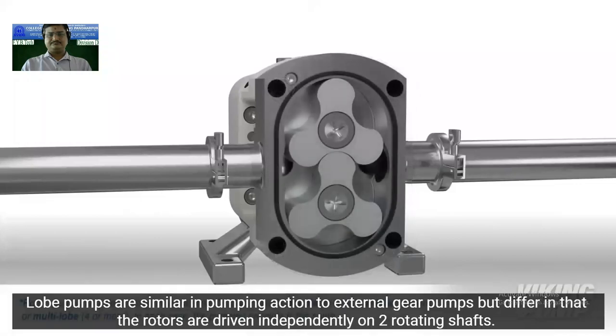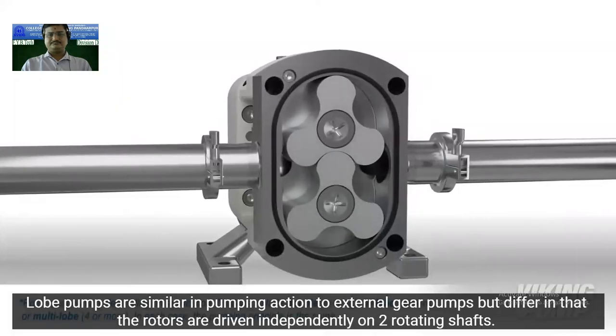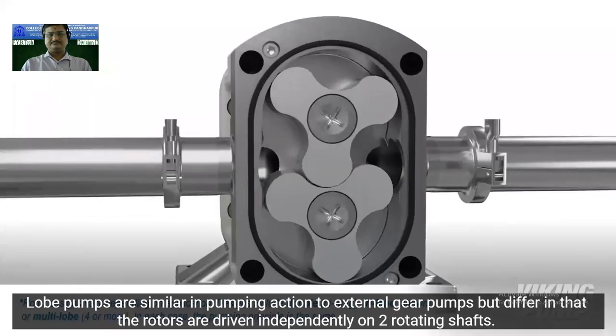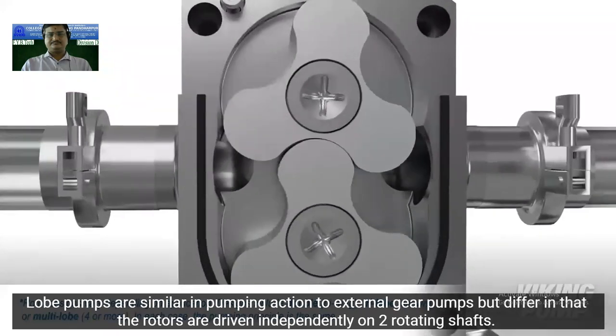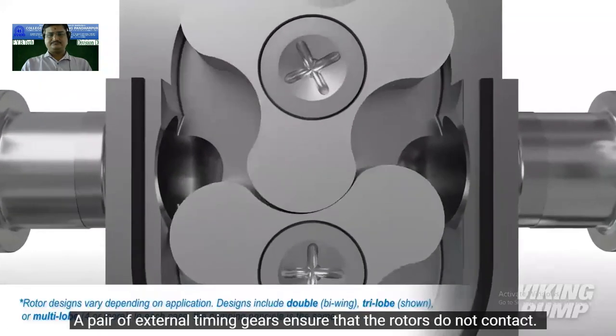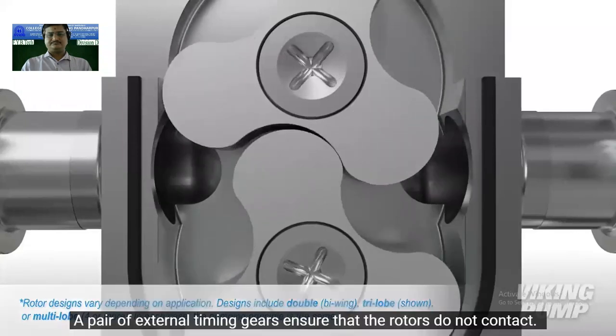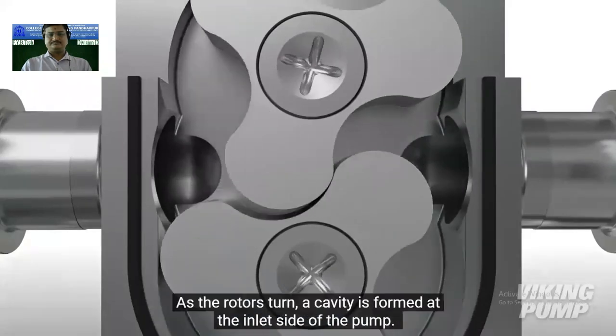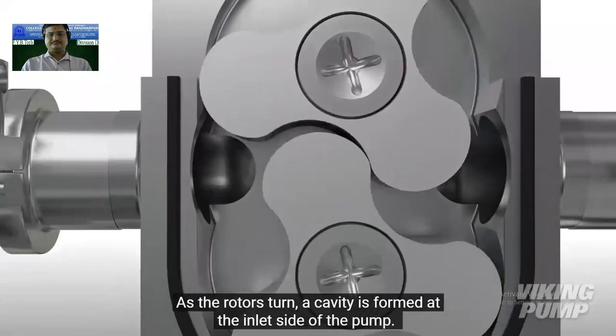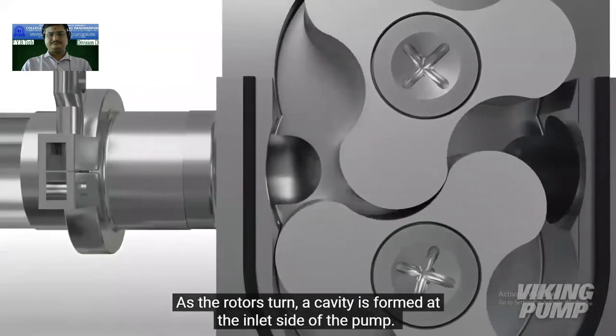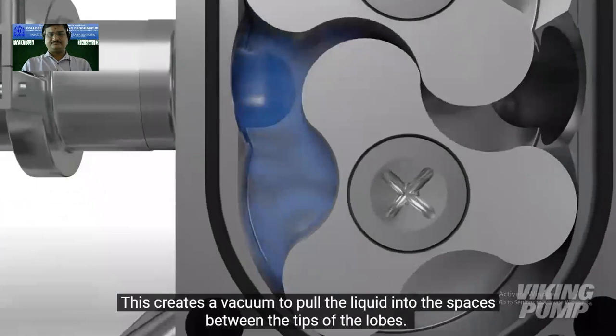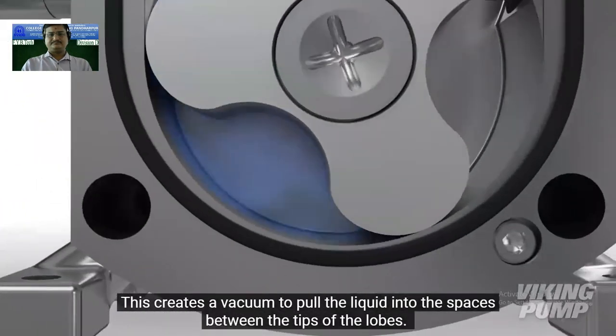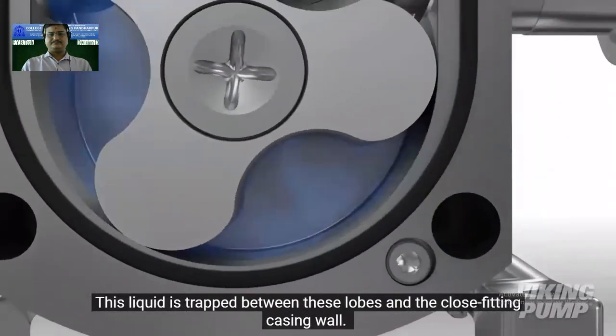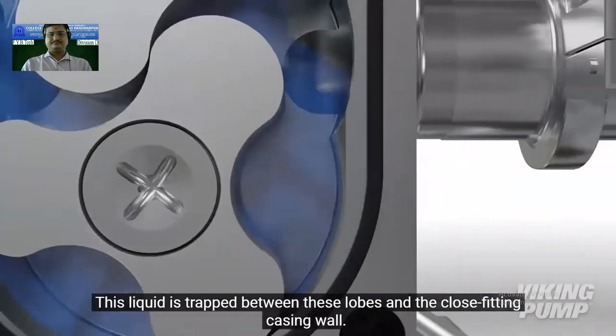Lobe pumps are similar in pumping action to external gear pumps, but differ in that the rotors are driven independently on two rotating shafts. A pair of external timing gears ensure that the rotors do not contact. As the rotors turn, a cavity is formed at the inlet side of the pump. This creates a vacuum to pull the liquid into the spaces between the tips of the lobes. This liquid is trapped between these lobes and the close-fitting casing wall.